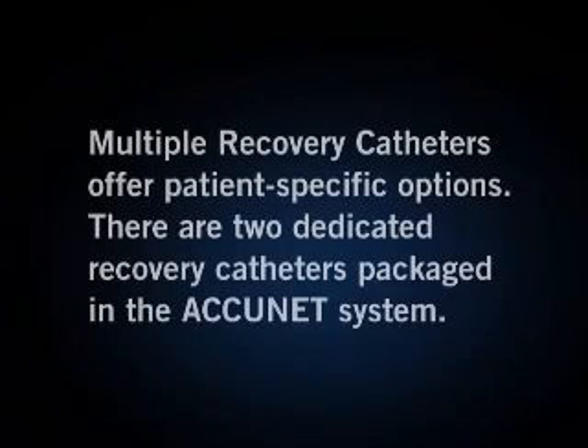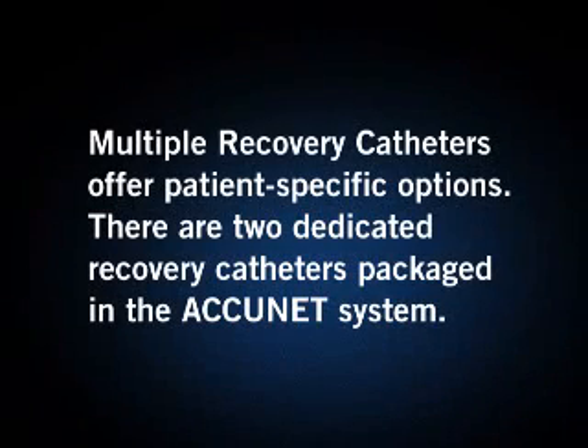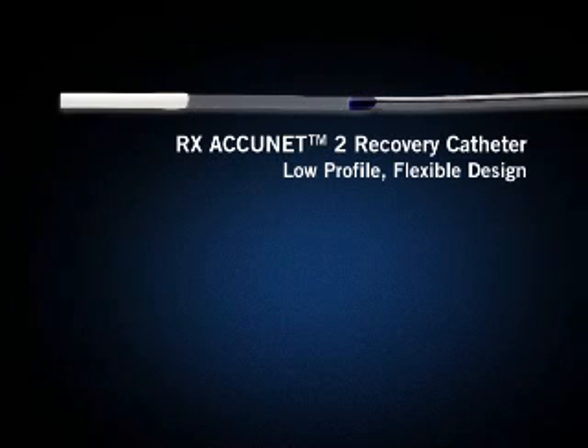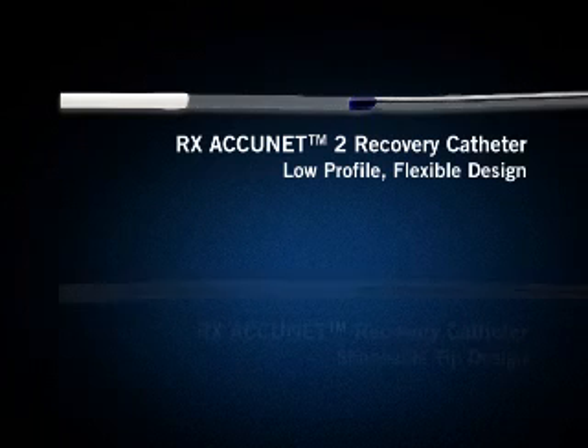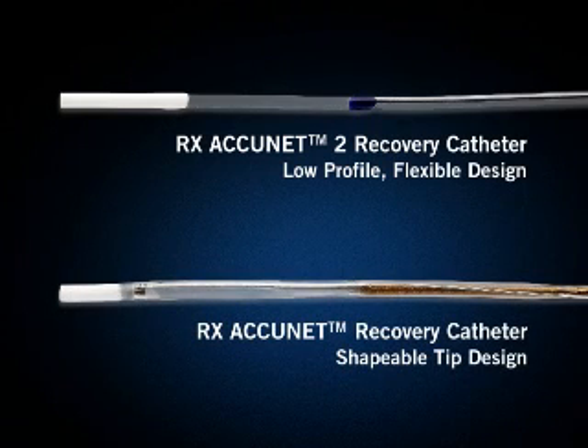Filter basket recovery. Multiple recovery catheters offer patient-specific options. There are 2 dedicated recovery catheters packaged in the Accunet system. The RX Accunet 2 recovery catheter has a lower profile, more flexible tip, and a more flexible catheter shaft, while the original recovery catheter has a shapeable tip that can be steered away from stent struts during advancement.